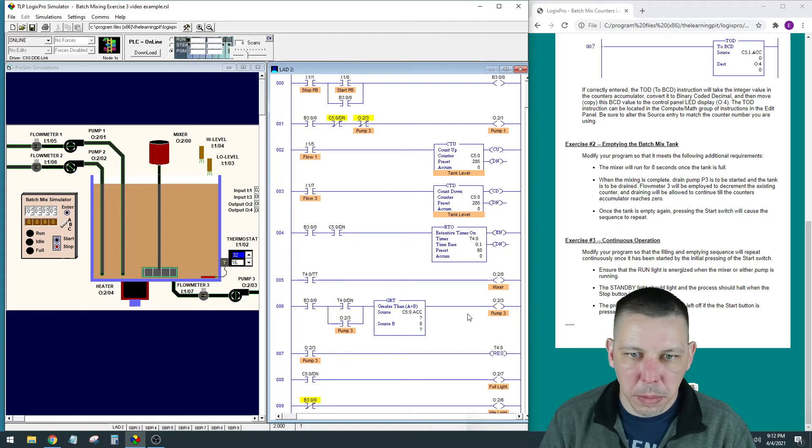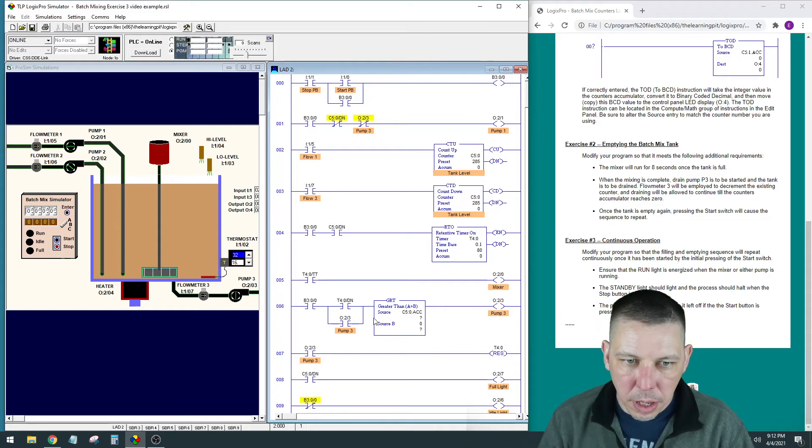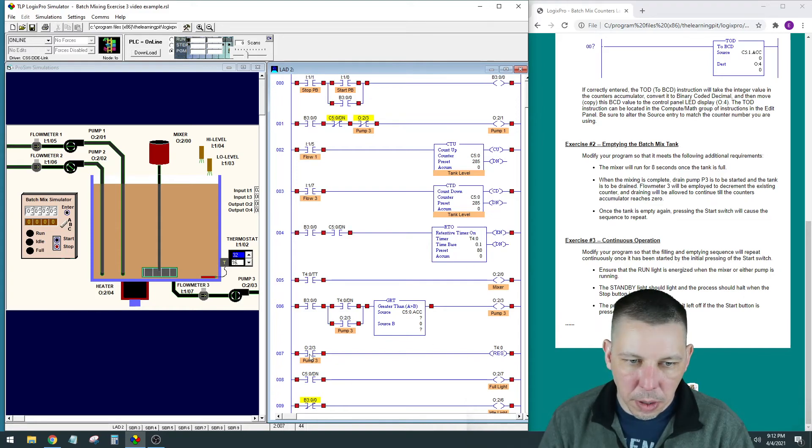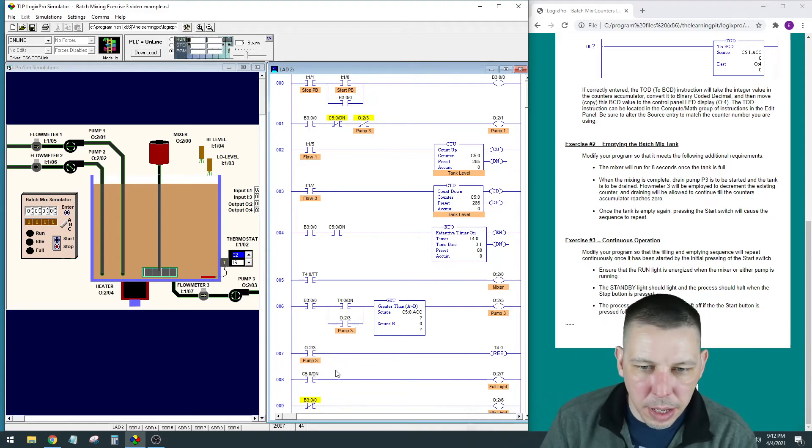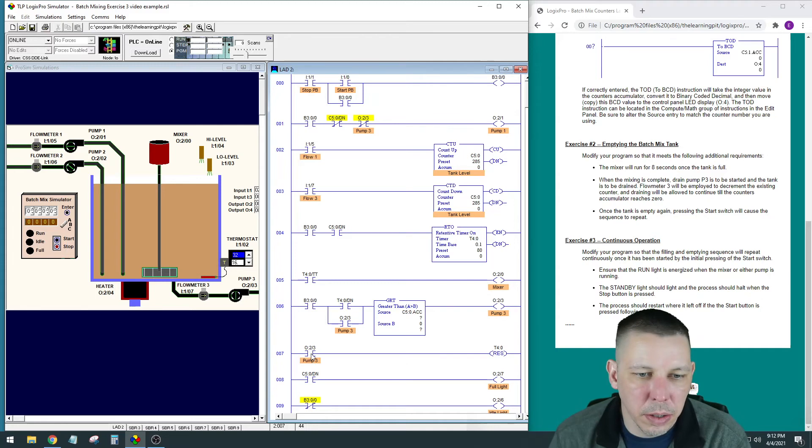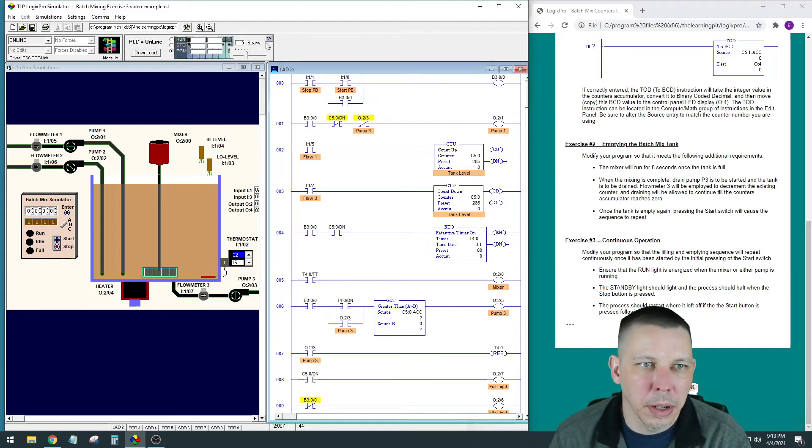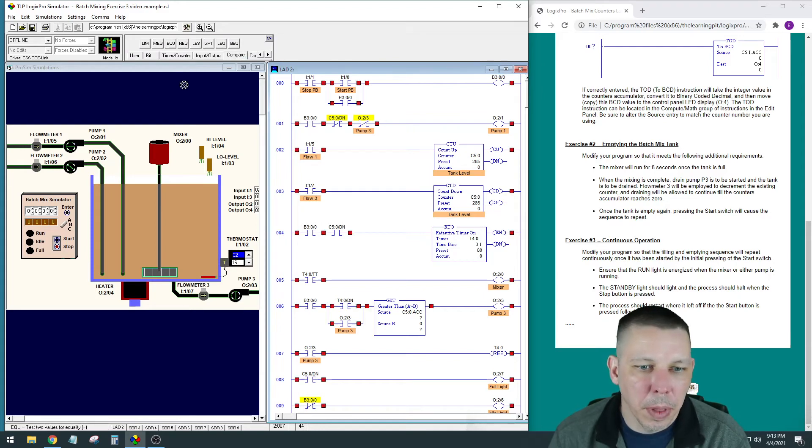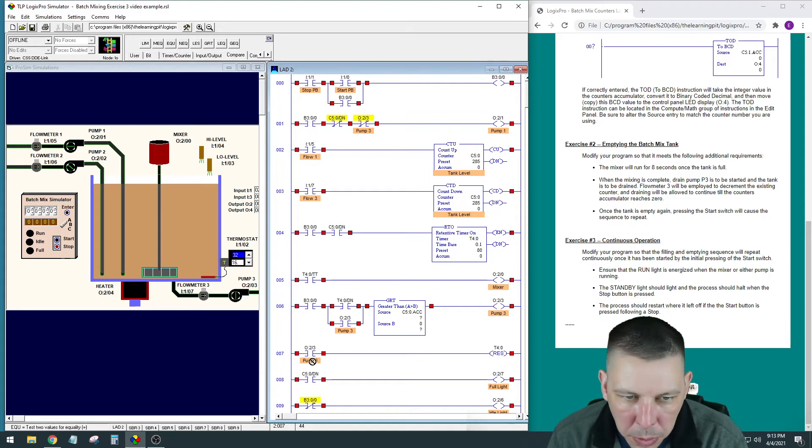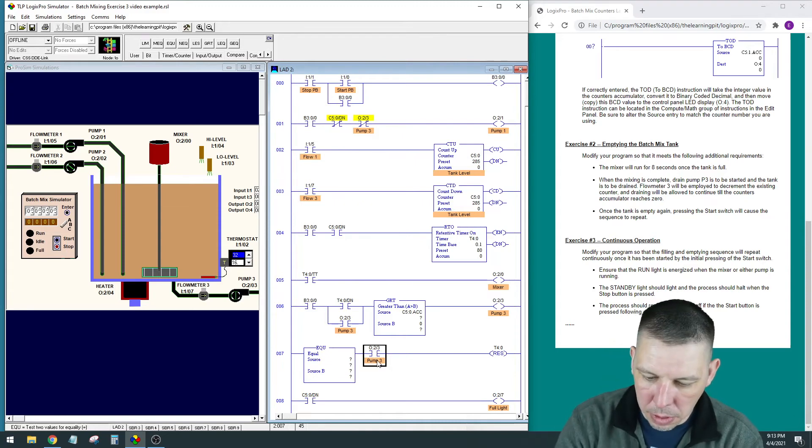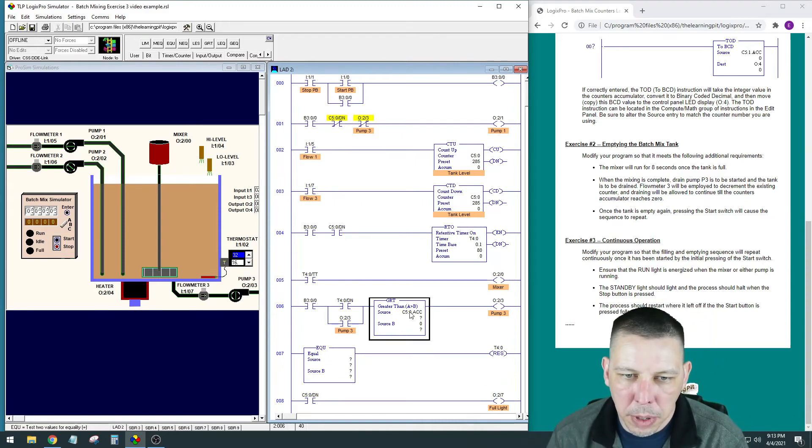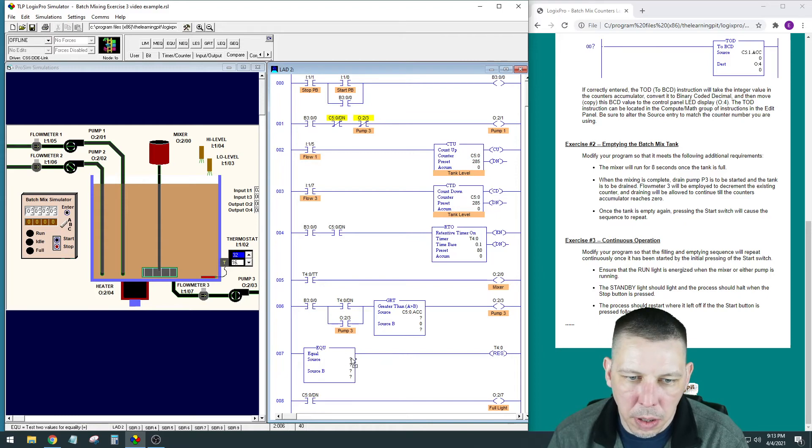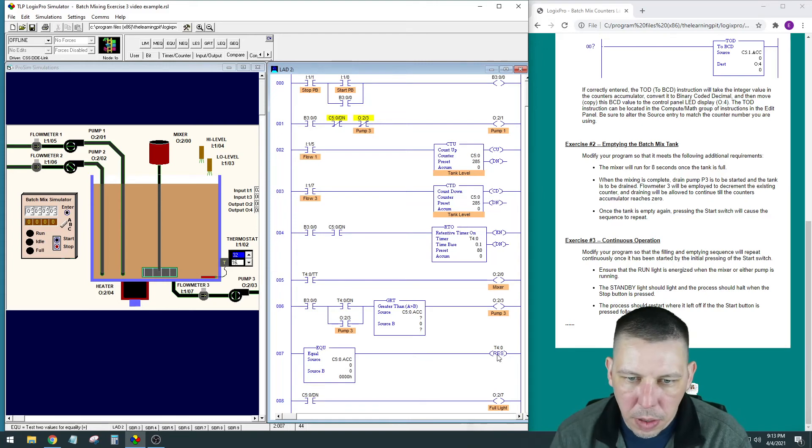I think I'm going to have to make some edits down here. I think I'm going to have to leave this T4.0 done longer. I'm going to have to have this T4.0 stay done, not be reset until the pump gets back down to zero. As I look at it, it's the only thing that really makes sense. I'm sure there's a bunch of other ways to do this, but this is the way I'm going to do it with my current incarnation. I'm going to have my accumulated and my source be B3:0/0—that'll reset my T4.0. So my T4.0 will stay done. Then I shouldn't even need this in here.